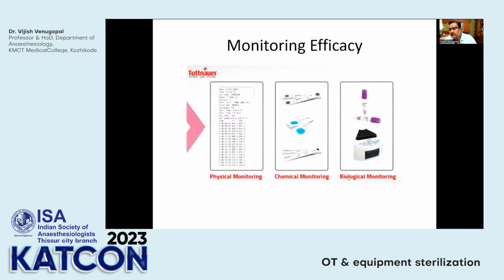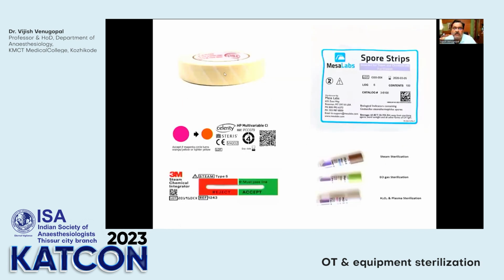Now, how do you monitor that this is efficacious? You can have physical monitoring. Suppose in an autoclave, you can look whether the temperature has reached, whether the pressures have come up. So that is on the dials. You can use chemical monitoring. You can use biological monitoring. Now, chemical monitoring is in the form of strips. Type 1 to type 6 strips. Type 1 is kept on the outside of the package, whereas type 3, 4, 5, and 6 are put inside the package. And you look at the color change as mentioned on the strip.